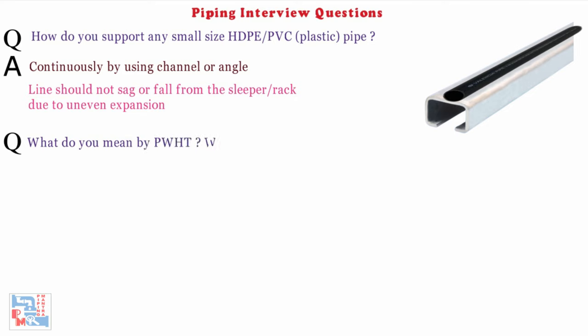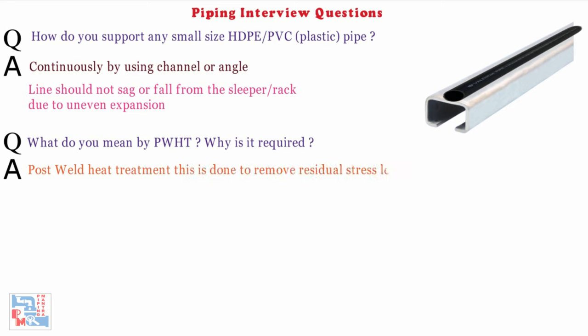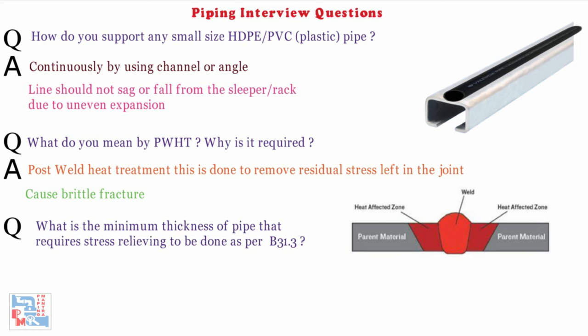Next: what do you mean by PWHT and why is it required? PWHT stands for Post Weld Heat Treatment. This is done to remove residual stress left in the joint, which may cause brittle fracture. Next: what is the minimum thickness of pipe that requires stress relieving? As per ASME B31.3, it is 19mm thick.